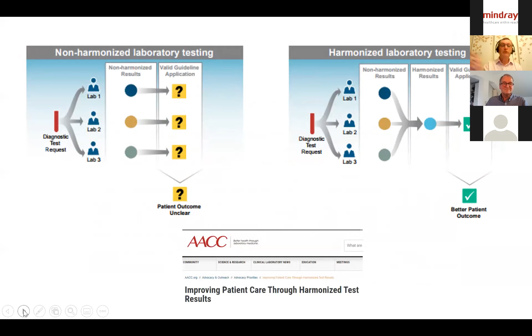So that's all about trying to harmonise results. There's a lot of work going on now, trying to ensure that situation doesn't occur, that laboratories are harmonised, so that the same sample requesting the same assay in two different laboratories will get the same answer. So that's exactly what I've got there. You want to make sure that one result comes out from 3 laboratories measuring the same thing, not 3. So that's about traceability, metrological traceability, and it's the property of a measurement result whereby the result can be related to a standard. So for a particular assay, if you're measuring creatinine, for instance, you would like all laboratories to have their method standardized against some universal standard, so that all methods really at their core are measuring creatinine in the same way.